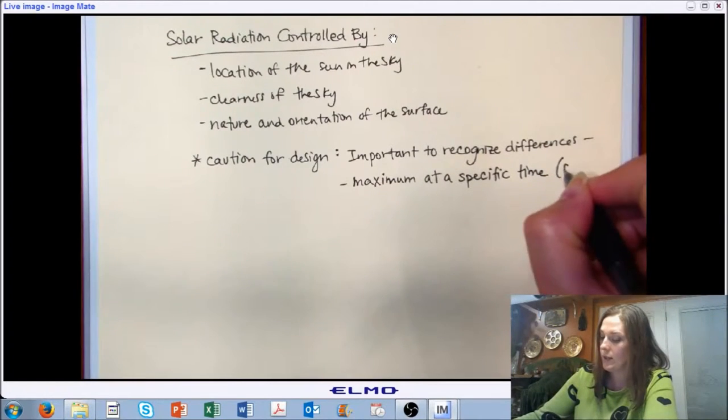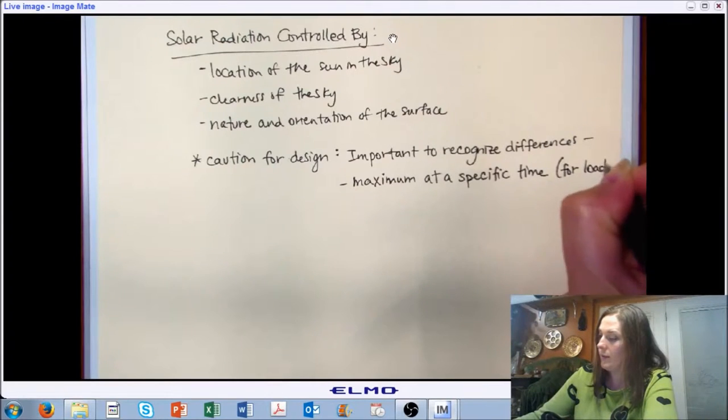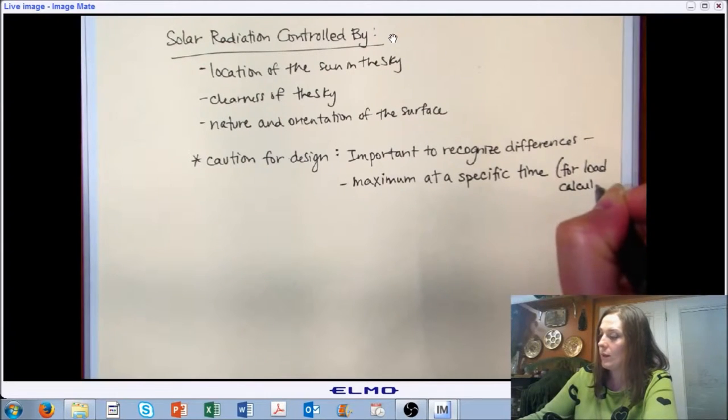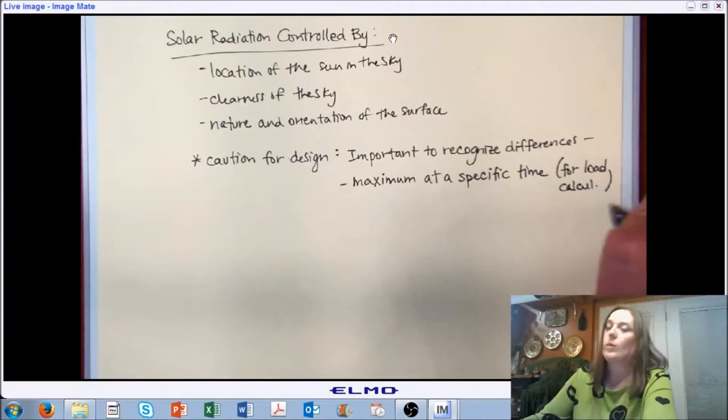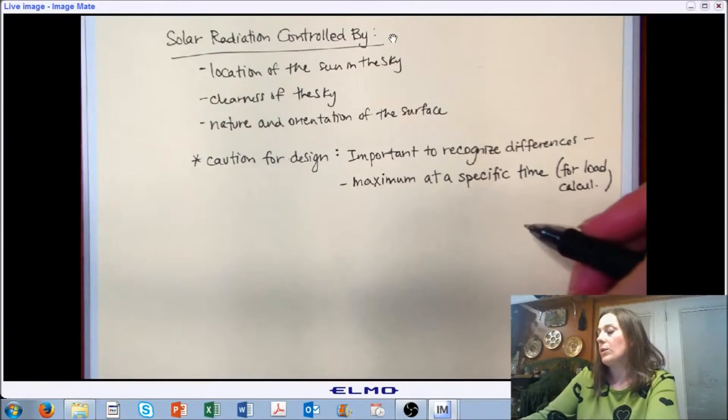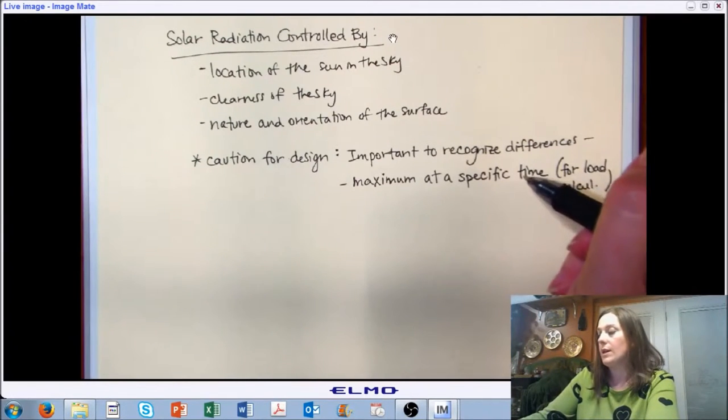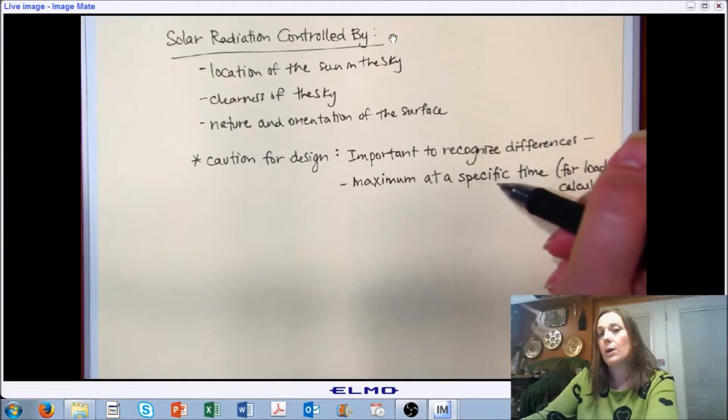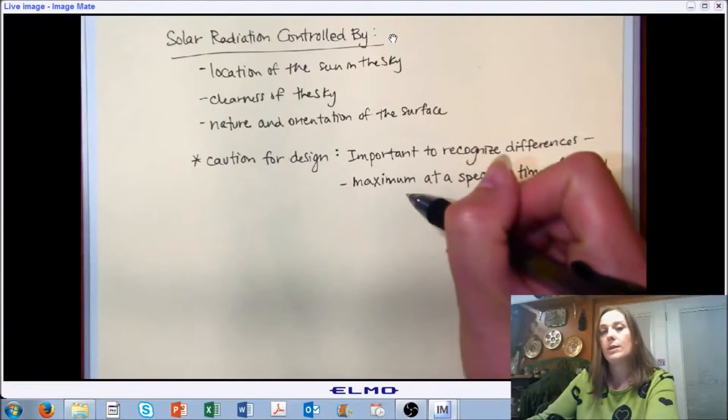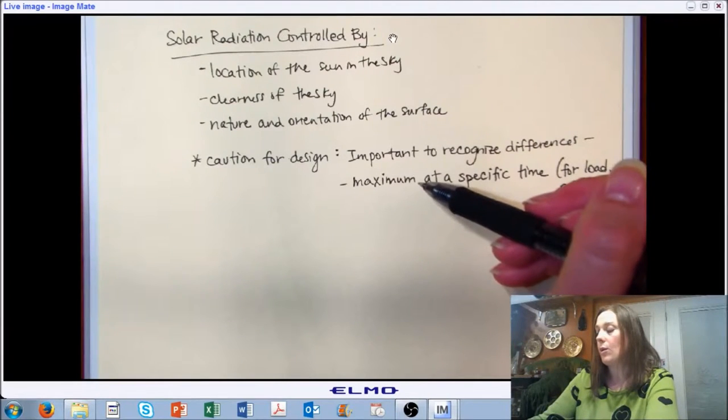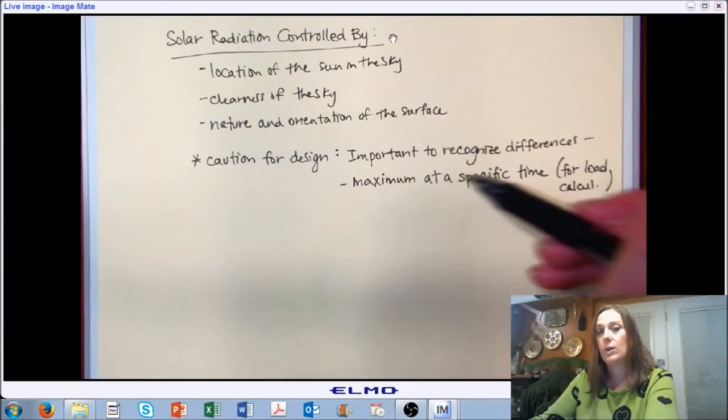We've already looked at this in previous chapters, not specific to solar radiation, but this approach. Whenever we're doing load calculations, we really want to think about worst case scenarios. You could look at solar radiation either as a load for your cooling system or as relief for your heating system. In which case you would need to consider, do you want maximum? Do you want minimum? How much can you always expect to be contributing? Or how much at the most extreme scenario do you need to account for?